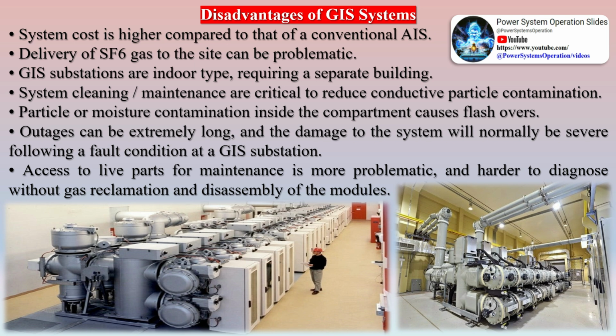Disadvantages of GIS systems: system cost is higher compared to that of a conventional AIS. Delivery of SF6 gas to the site can be problematic. GIS substations are indoor type, requiring a separate building. System cleaning and maintenance are critical to reduce conductive particle contamination. Particle or moisture contamination inside the compartment causes flashovers.